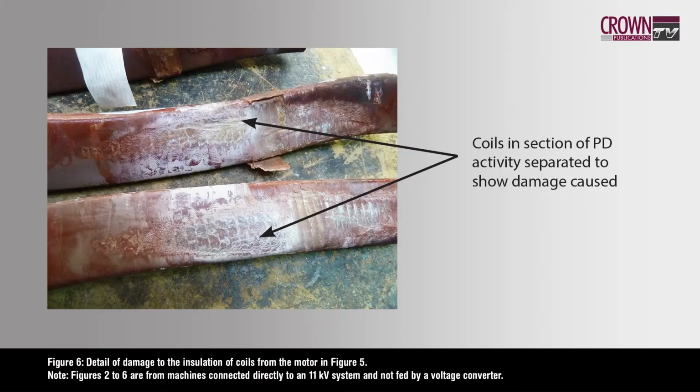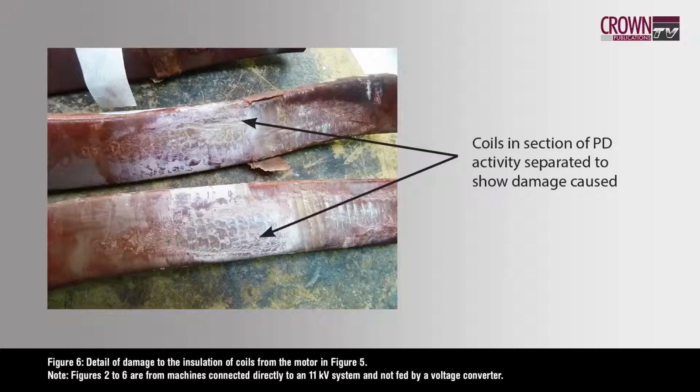The other photographs that we have there show very short life, and basically my interpretation of this is the coils were badly formed and the gap between the coils wasn't uniform. So the stresses were excessively high. And in a matter of a few years, these are only a couple of years old, you can see how much damage was done in the coil at that particular stage.